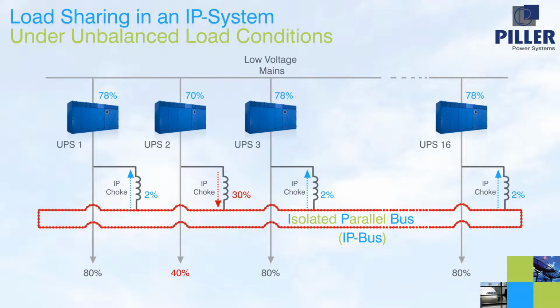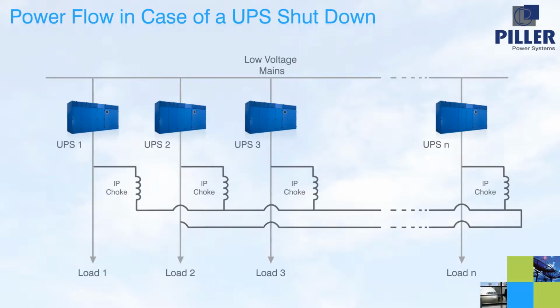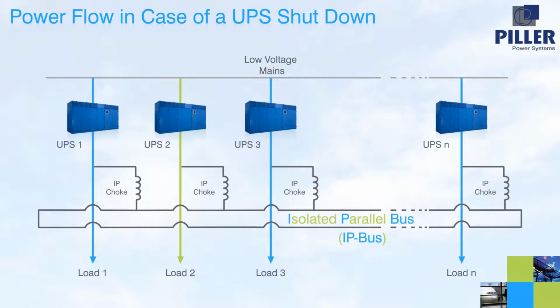Once again, the load sharing is driven by the common phase angle between utility and IP bus, and the different load-dependent phase angles across each UPS, so that the sum of the phase angle across each UPS and its IP choke is equal to the common phase angle between utility and IP bus. This simple power distribution method via the IP bus applies in other scenarios, including that of a sudden UPS failure or shutdown. In this situation, the associated load is instantaneously redirected and supplied from the IP bus through the IP choke, without relying on the function of switching devices.